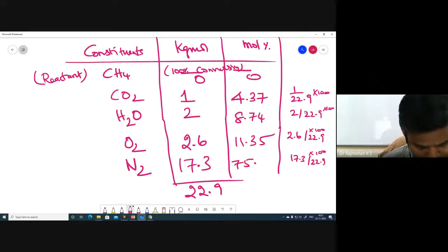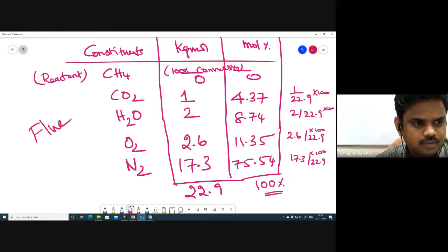1 divided by 22.9, multiplied by 100. What you get is 4.36 percent. The amount of CO2 is 4.37, I can make it that. Similarly, the percentage for 2 is 2 times this, 8.74. This is 2.6, you get 11.35. And 75.54. You should check that the total comes to 100%. So this is the flue gas analysis.